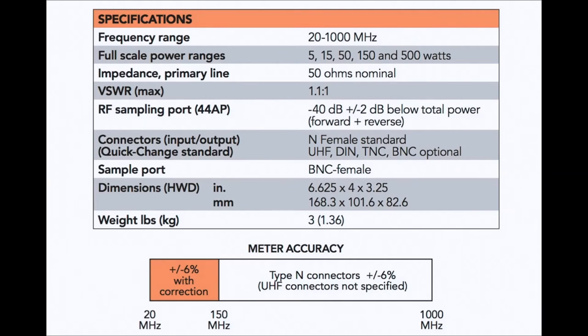In review, the specifications for this meter, the Model 44A or 44AP are as follows: 20 to 1,000 megahertz, 5, 15, 50, 150, and 500 watts full scale. 50 ohms nominal. 1.1 to 1 is the VSWR max for the device. The sampling port is 40 dB down, plus or minus 2 dB, for monitoring purposes. Comes with standard N female on each side. You can get UHF connectors, DIN connectors, TNCs, BNCs as options. Sampling port is a BNC. The meter accuracy is plus or minus 6% if you use the correction factors. Above 150 megahertz, it's plus or minus 6% overall.